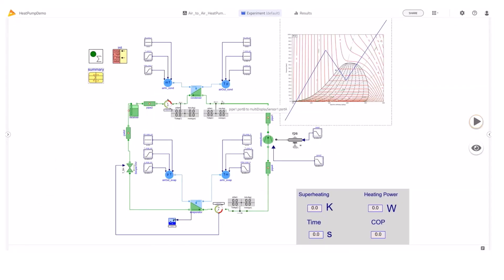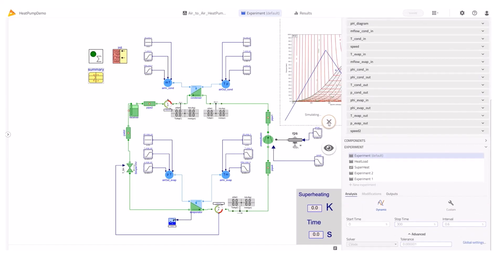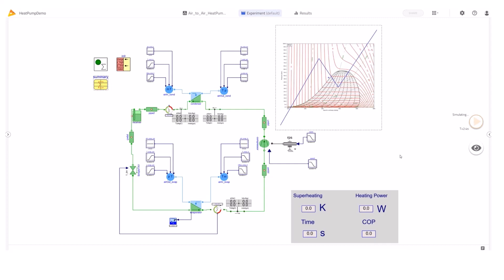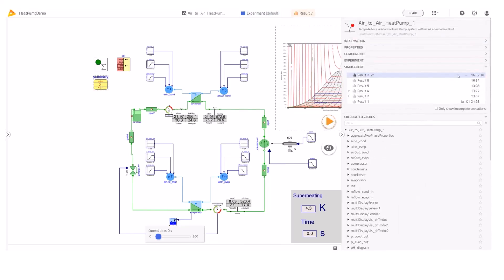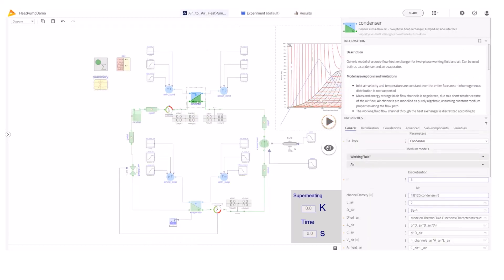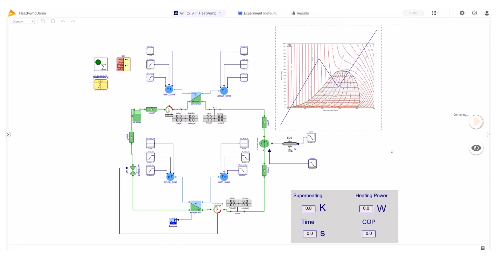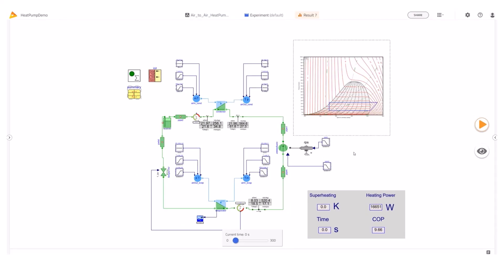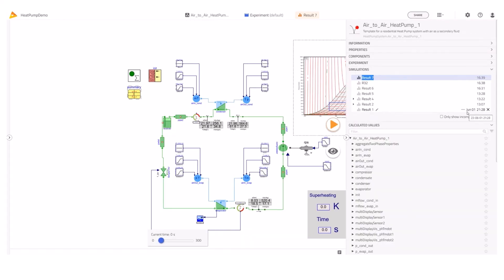Lastly, let's explore how the system would perform when using a refrigerant with even lower GWP — propane. I'll first run the system using R32 and the optimized size for the condenser. I'll save the results with the name 'R32.' Now I click on a component, for example the condenser, and change the refrigerant to propane. Then I click on 'Propagate.' This will change the working fluid at the different components of the system and thus simplify the process. Now I click on 'Simulate.' For comparison, I'll rename the results to 'propane' and I'll plot the COP.